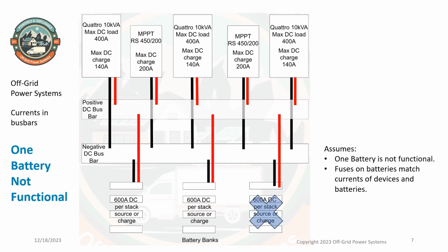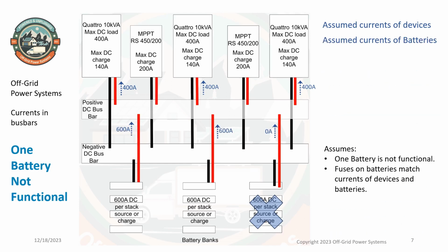So what happens if one of the batteries fails? Again, we start with all Quattros requiring 400 amps. Now only two of the batteries are providing current, 600 amps each. This is a precarious situation since they are at their max, and the system would completely fail if the fuse on one of the remaining batteries fails.